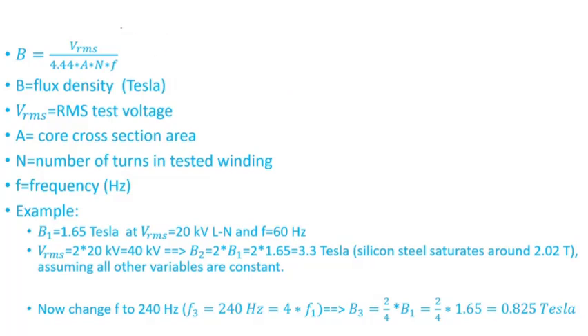Here's the equation that relates the flux density, the RMS voltage, number of turns, frequency, and so forth. B equals V_RMS divided by 4.44 times A times N times f. B is the flux density in Tesla. V_RMS is the RMS test voltage. A is the cross-section area of the core. N is the number of turns of the winding to which the voltage is applied. f is the frequency in Hertz.